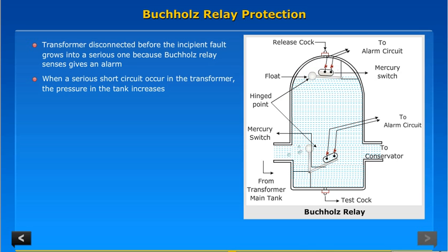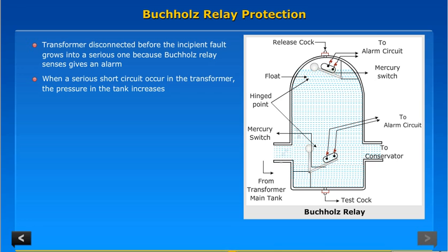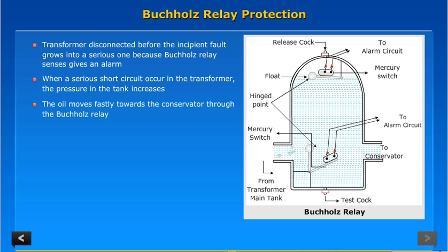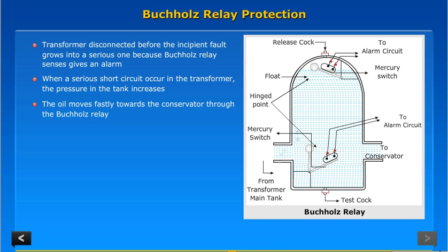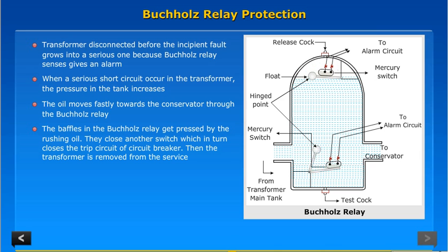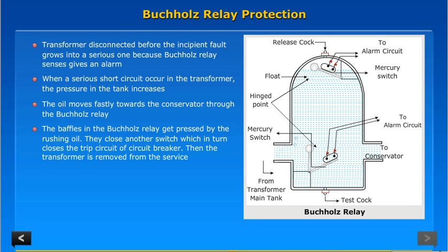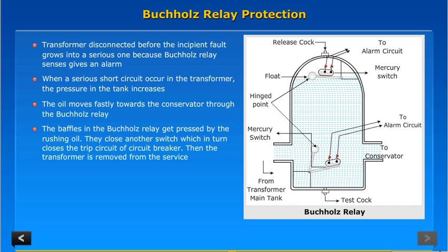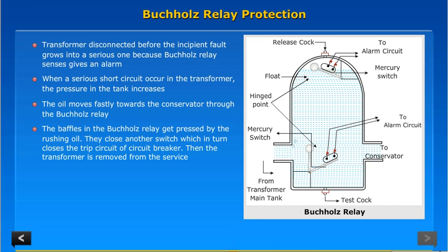When a serious short circuit occurs in the transformer, the pressure in the tank increases. The oil moves quickly towards the conservator through the Buchholz relay. The baffles in the Buchholz relay get pressed by the rushing oil. They close another switch, which in turn closes the trip circuit of the circuit breaker, and the transformer is removed from service.